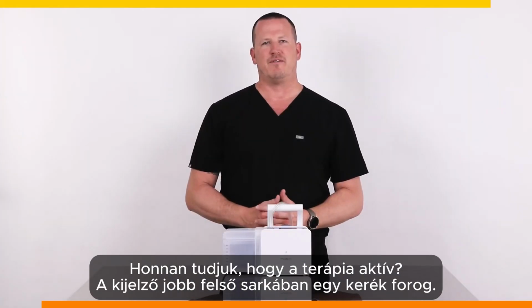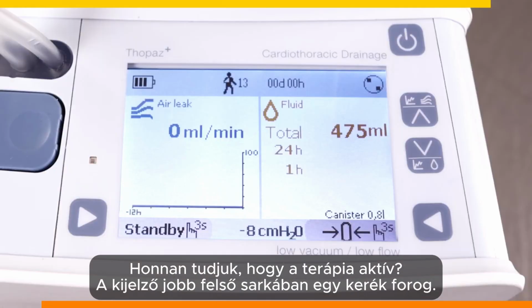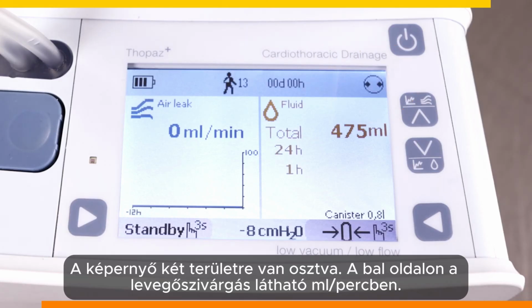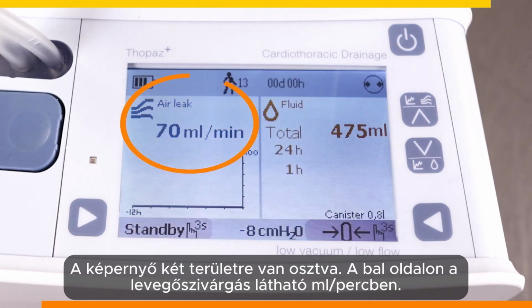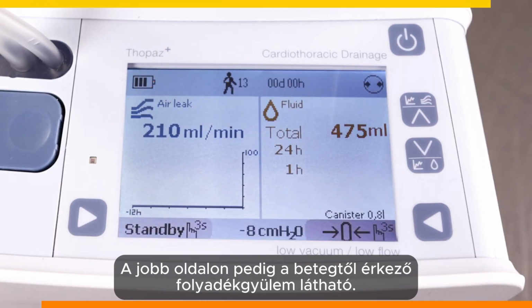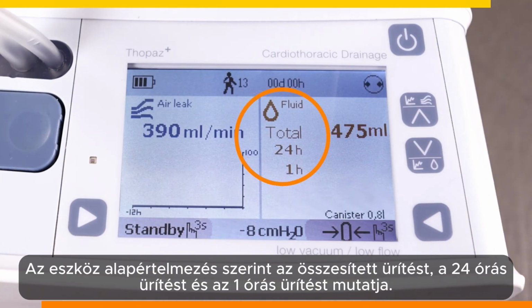So how do we know if therapy is active? In the top right-hand corner of the display, there is a wheel that is rotating. On the display, you can see that the screen is split into two areas. On the left shows the air leak in milliliters per minute, completely different than counting bubbles. And on the right is the fluid drainage from the patient. And the device is defaulted to show the total drainage, 24-hour drainage, and 1-hour drainage.